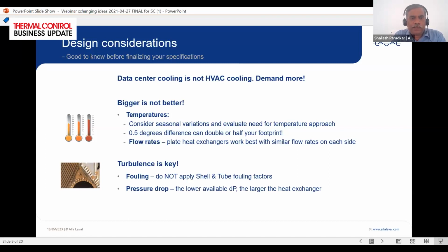Pressure drop is another important aspect. Alfa Laval can convert this pressure drop into heat exchanger efficiency. A lower pressure drop needs a larger heat exchanger, but we need to find a balance by trying various flow rates and duty conditions to arrive at a good pressure drop that is power saving and gives an optimized heat exchanger as a result.